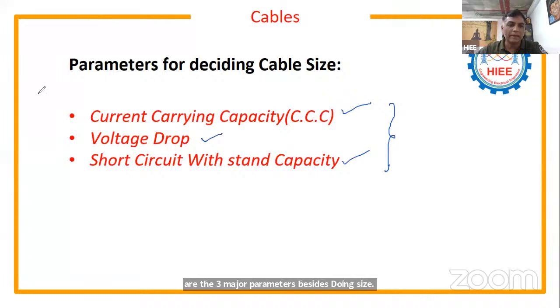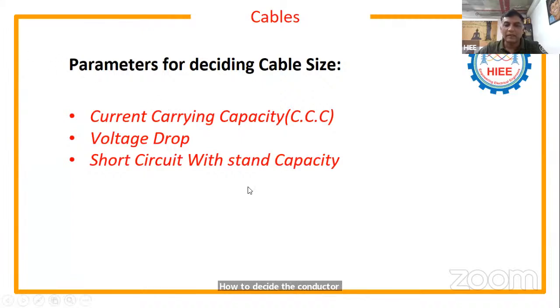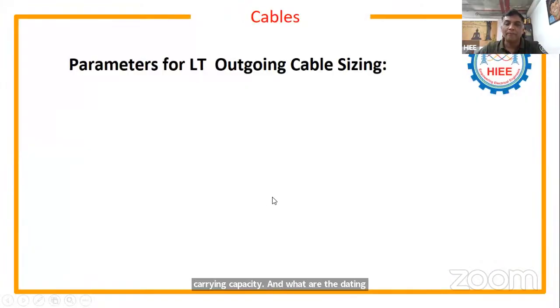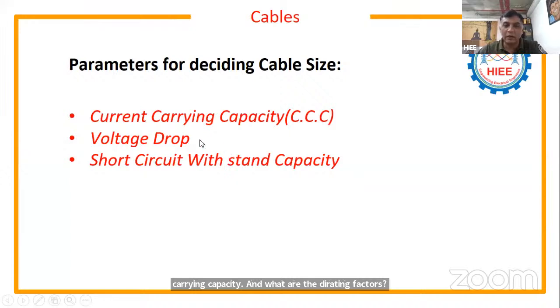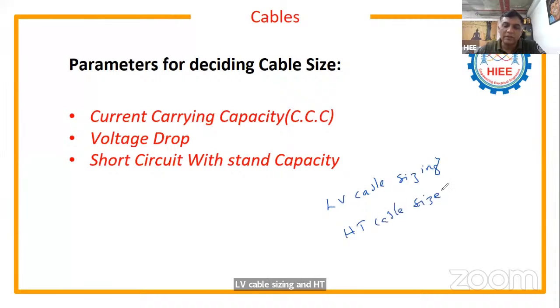Okay, so the point here is how to decide the conductor size based on the current carrying capacity, and what derating factors we have to consider, and how to calculate the voltage drop and what formulas we use to calculate it. And in the cable sizing calculation, you have two things: one is LV cable sizing and HT cable sizing. Generally, LV cable sizing is decided based only on current carrying capacity and voltage drop, whereas for HT cable sizing, we also consider short circuit withstand capacity as a major parameter.